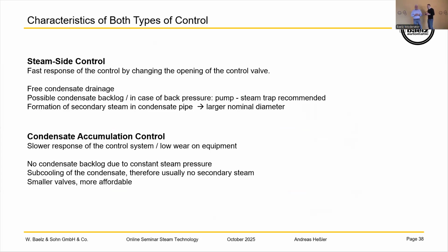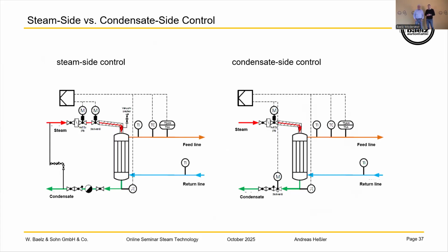Just to make it clear, because I think this is a very interesting slide that you just showed: the steam side and the condensate side control. We're making a difference between two types of controlling the power that the steam terminal provides to the secondary side. On the steam side control, we control the amount of steam getting into the heat exchanger by a control valve on the steam side, correct. And the condensate goes away.